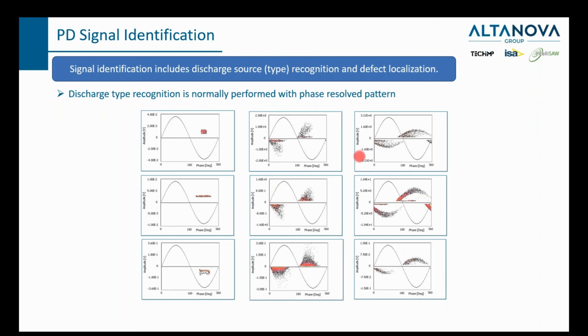The surface and internal discharge we can also distinguish by the shape of the distribution, whether the peak of the distribution is smooth and follows the voltage waveform, or, for the surface discharge, the peak is scattered a lot and doesn't go beyond the zero crossing, while the internal discharge goes beyond the zero crossing. It would take a long time to explain the reason why different defects have different phase resolved patterns. In general, this recognition heavily relies on the experience and training the operator has. Each service provider or equipment provider should have a library of phase resolved patterns as a reference.